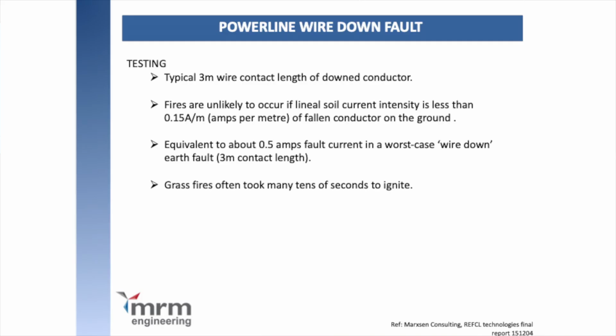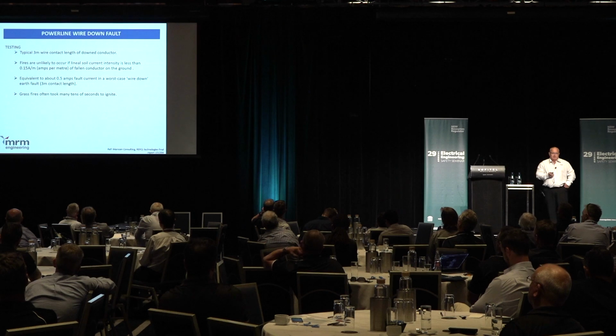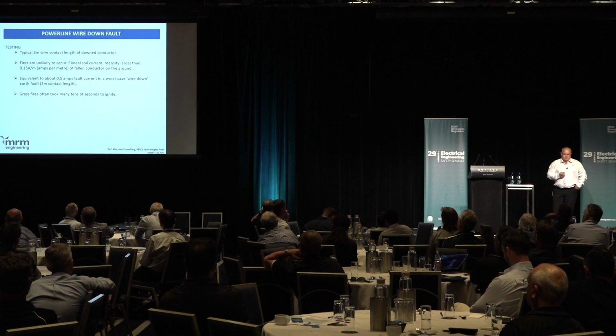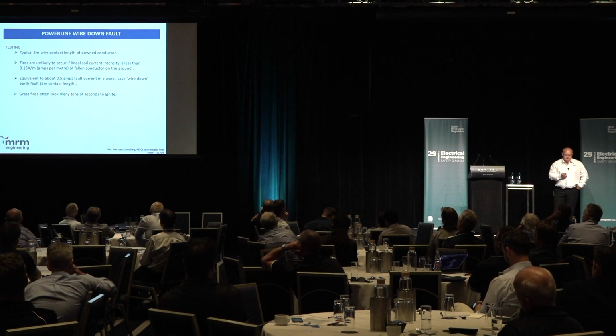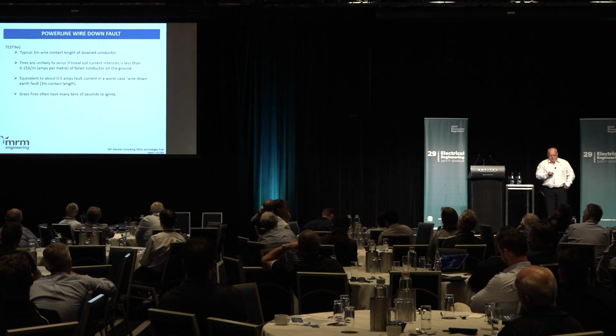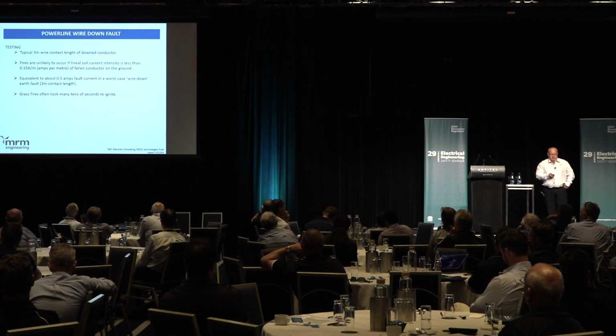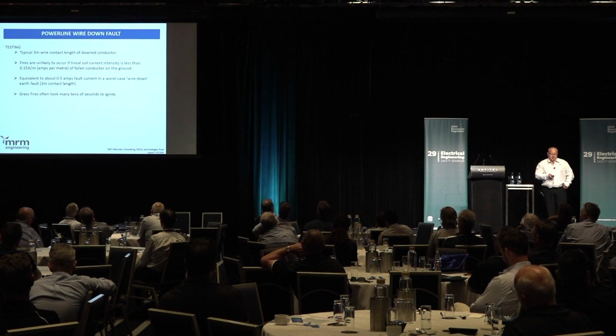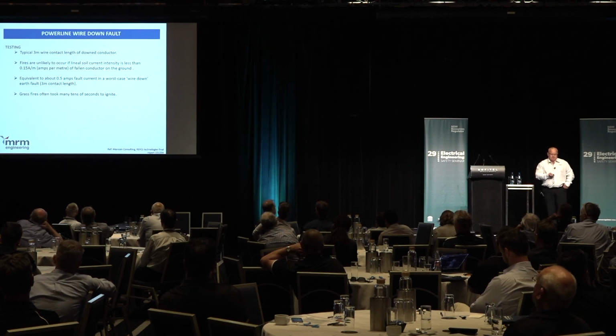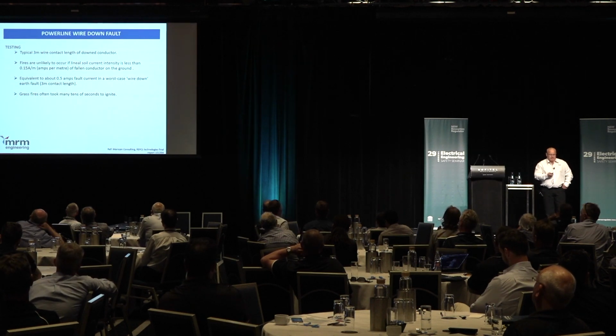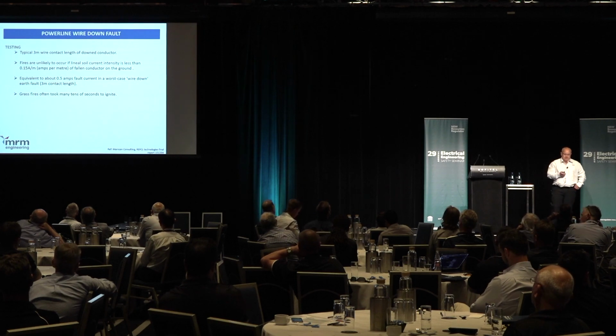So for the analysis they use for the typical wire down to ground, they use the 3 metre contact period, or contact length. So when the power line falls down to the ground, they've estimated that the standard first touch is around 3 metres, and that gives you a current density of about 0.15 amps per metre. So what they did, they took that and converted it into 0.45 for the 3 metres. So they took a higher value of 0.5 amps for the worst case wire down fault. And that's what they need to achieve to prevent grass fires. A standard grass fire can take many seconds to ignite.